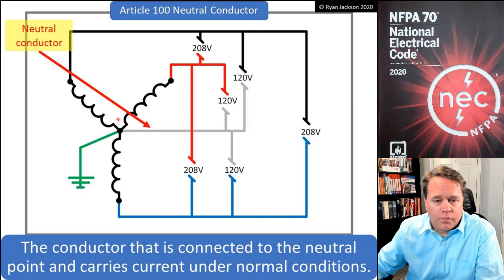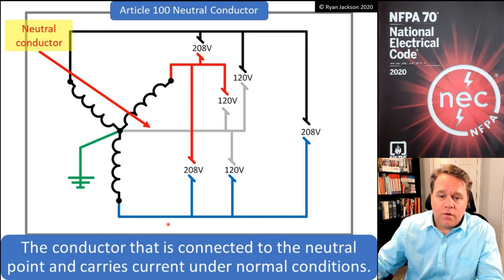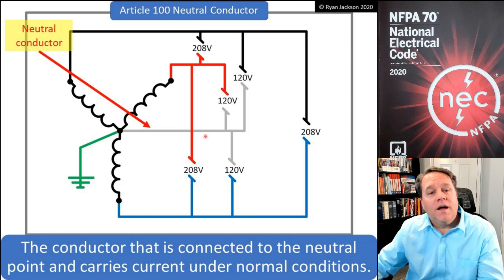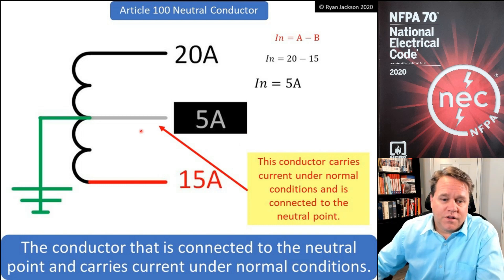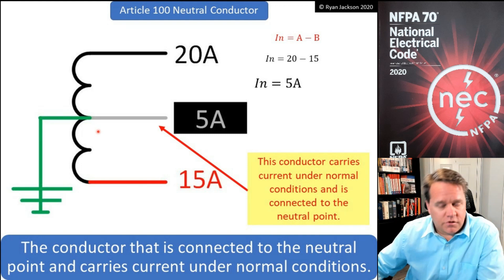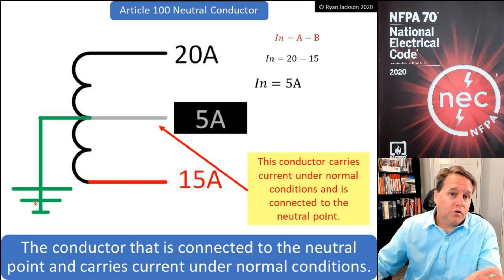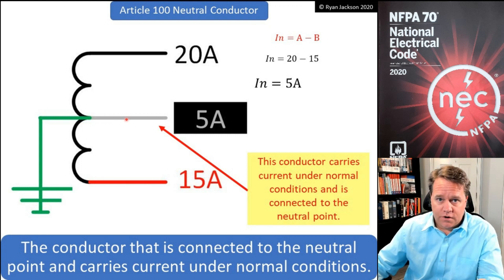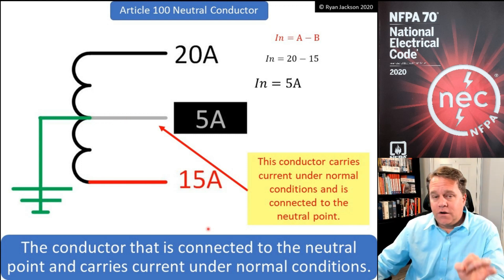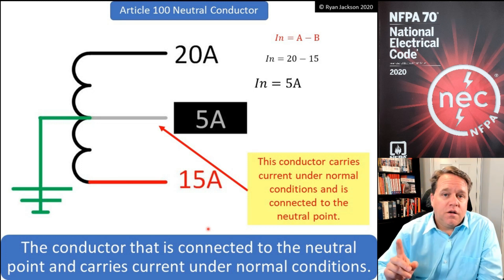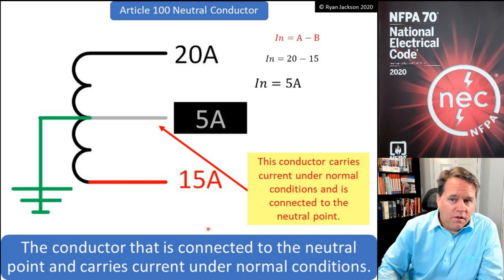This white wire here is connected to the neutral point and carries the unbalanced load of the three-phase conductors — that's our neutral conductor, because it connects to the neutral point and carries current under normal conditions. If these systems are solidly grounded, as shown by the grounding symbol, then that's a grounded conductor and it is also a neutral conductor. However, not every grounded conductor is a neutral conductor, because some grounded conductors do not connect to a neutral point.